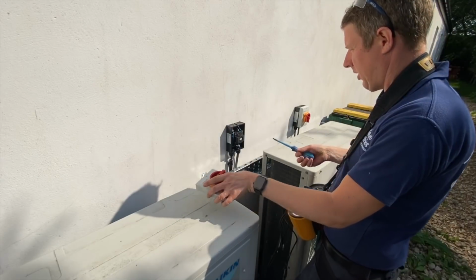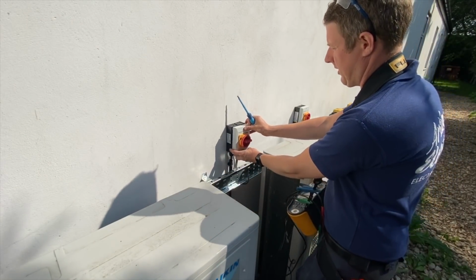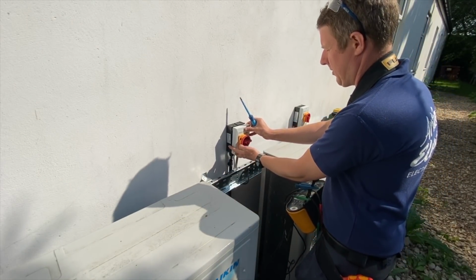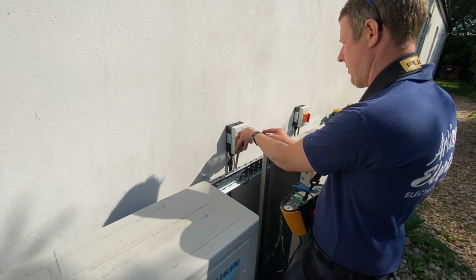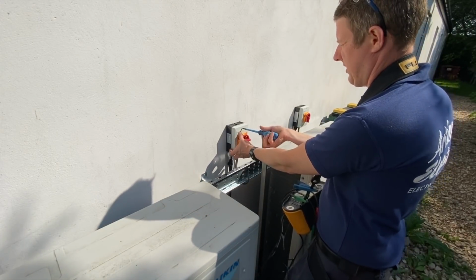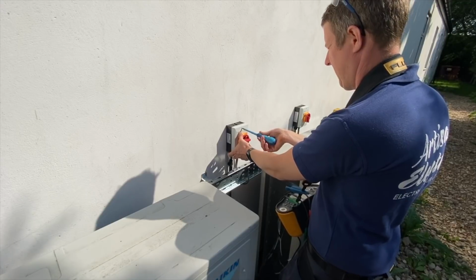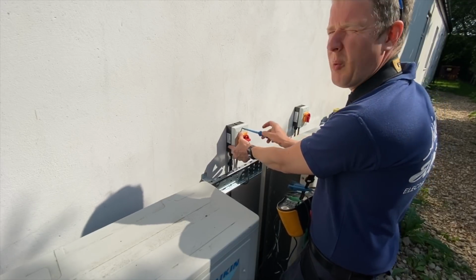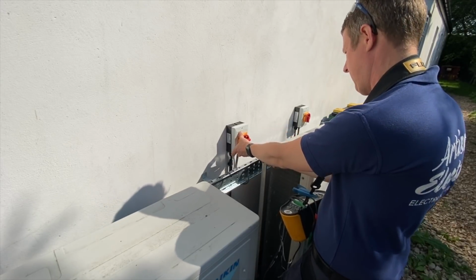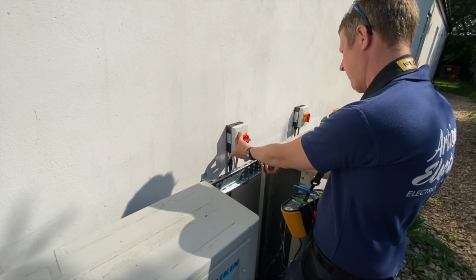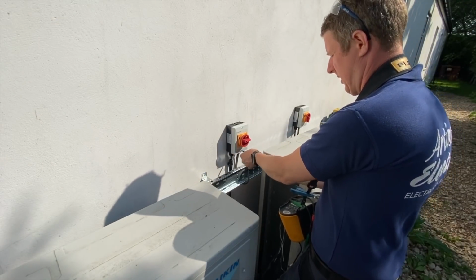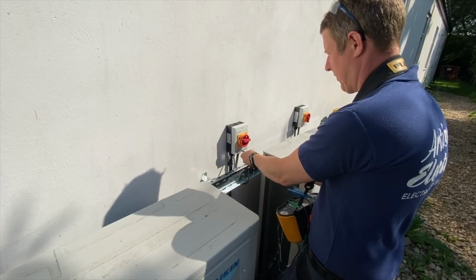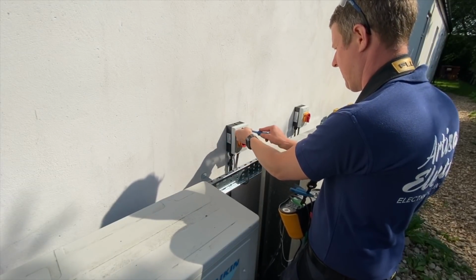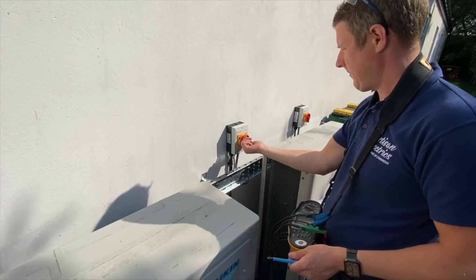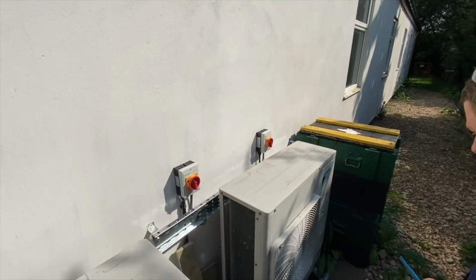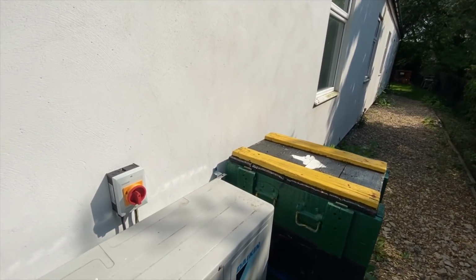There is a table of maximum readings that you have to abide by. This is a 32 amp type B circuit breaker for this one, so it's 1.15 ohms I believe for this size of breaker. So 0.43 is way below the maximum, which is great. And we can do the same for this one.